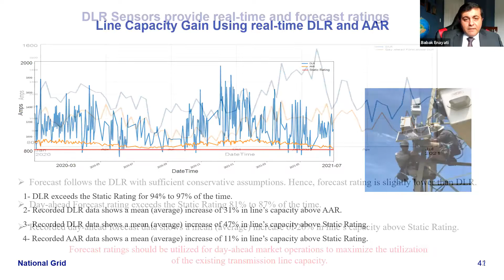As mentioned earlier, DLR gives us both real-time and forecast data, and forecast has a higher chance of being adopted in operations, both market and system operations. Our sensors give the same level of information; comparing DLR with forecast, the forecast follows DLR with a good trend. Because our forecast assumptions are more conservative, we see a good safety margin, and forecast rarely exceeds the actual DLR, showing the line remains safe if forecast is adopted.